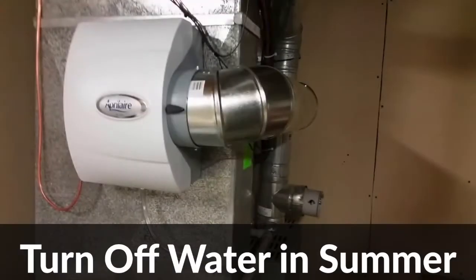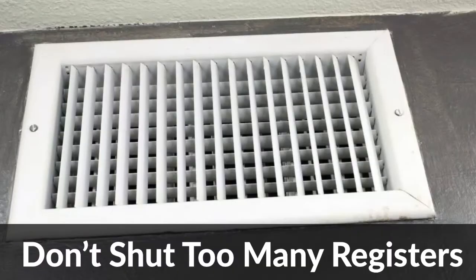And in the summer, you want to turn off water supply to your furnace's humidifier. There's no reason to keep a humidifier running in the summer. So when the weather starts to cool in the late summer or the early fall, and you're thinking about turning on the heat, you can install a new filter and set your humidistat to around 40% humidity, then turn on your water supply. And finally, don't shut too many registers. You never want to shut more than about 20% of your home's registers. If you do, you're going to put an unnecessary burden on your system by forcing it to work harder to give you the level of heat or cooling that you want.